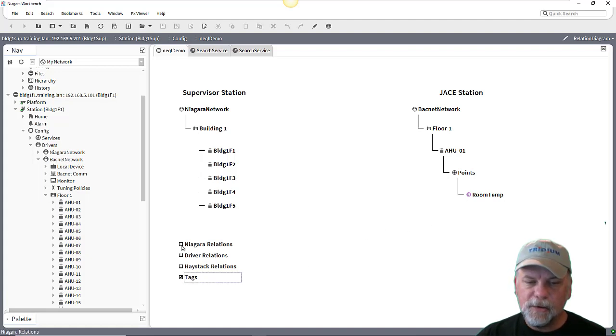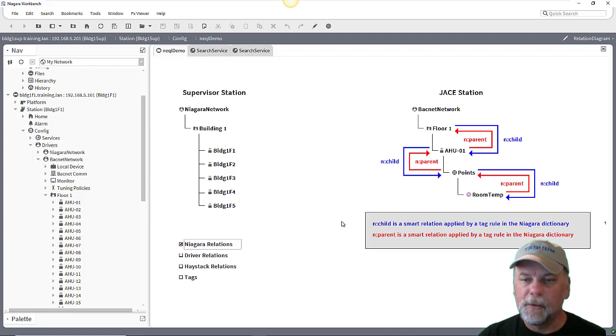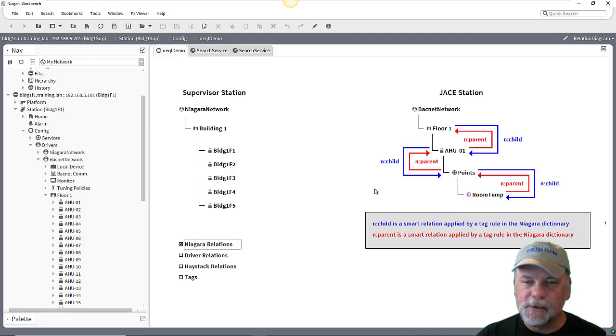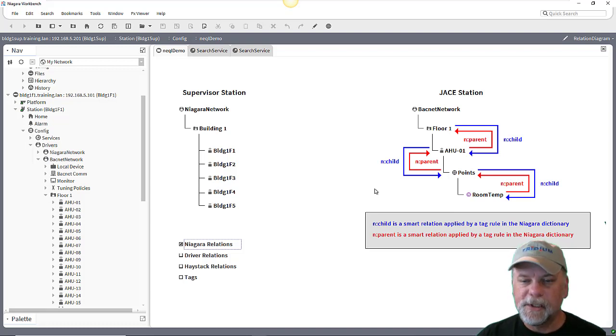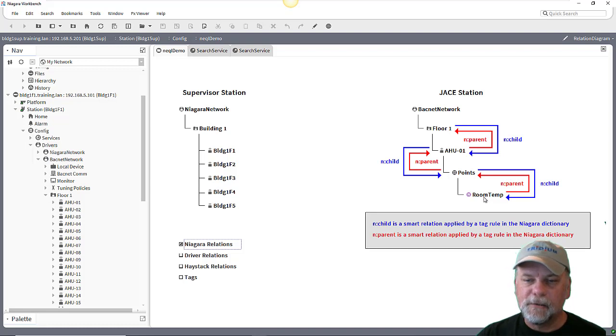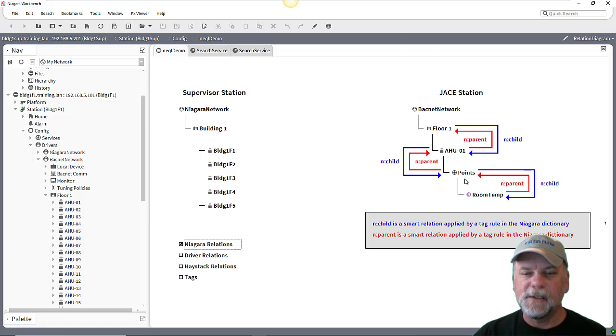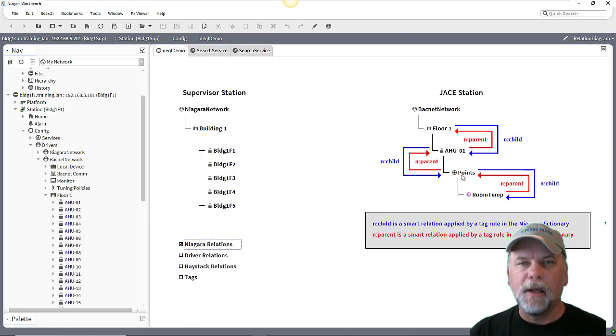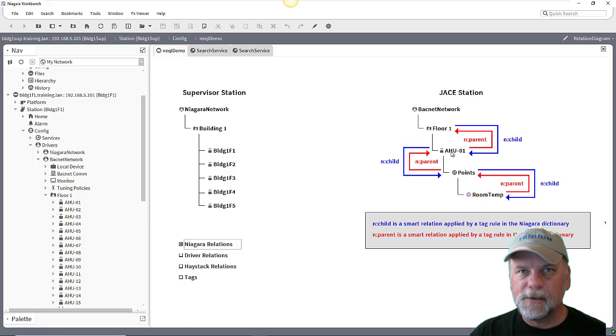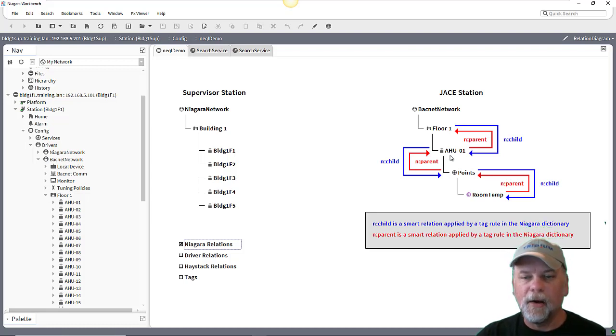Now if I wanted to look at just some specific points, maybe from air handler one, that's where I might need to also think about traversing a relation. What we mean by traversing a relation is I find the point and I can traverse the relation, maybe the n colon parent relation to its parent, to the points container, and then traverse the parent relation again up to the air handler device so that I could check maybe the n colon name tag on the air handler.